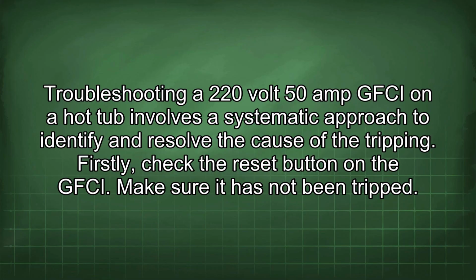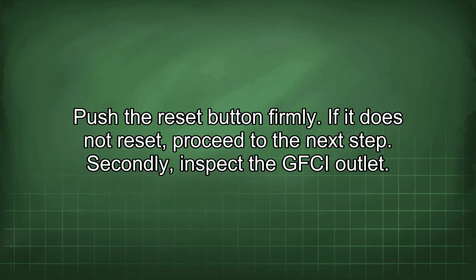Troubleshooting a 220-volt 50-amp GFCI on a hot tub involves a systematic approach to identify and resolve the cause of the tripping. Firstly, check the reset button on the GFCI. Make sure it has not been tripped. Push the reset button firmly. If it does not reset, proceed to the next step.